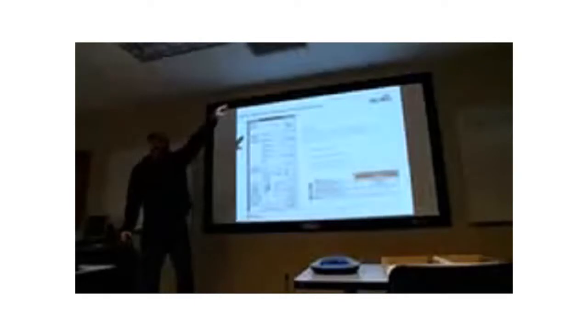So just taking a break from this for a minute, where do you think you find low pressure duct in your buildings? Registers. Yeah. The velocity coming out there is relatively low. It's probably about 500 feet per minute out of that diffuser if designed right. The duct we're going up to, are these VAV terminal units here? Gas packs. Oh, they're gas packs, so they're constant volume, right? Yeah. So that ductwork going back up to that unit is probably low pressure, probably around 1,000 feet per minute, something like that. Exhaust fans, right? Toilet exhaust, typically low pressure duct, right? Maybe half an inch, maybe an inch of static, something like that.